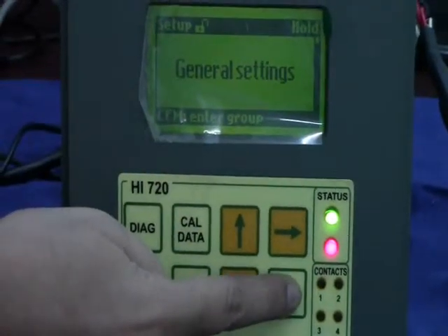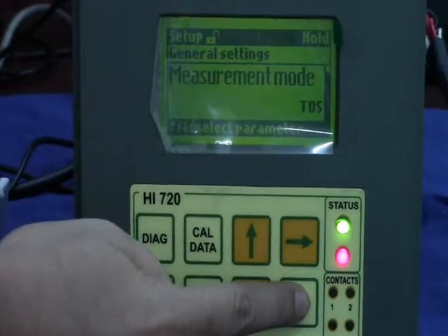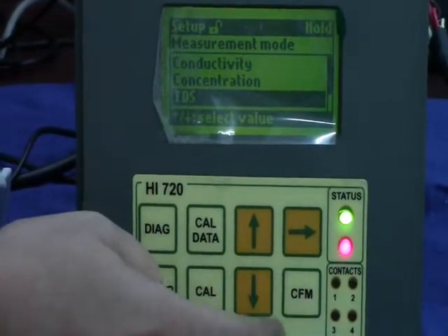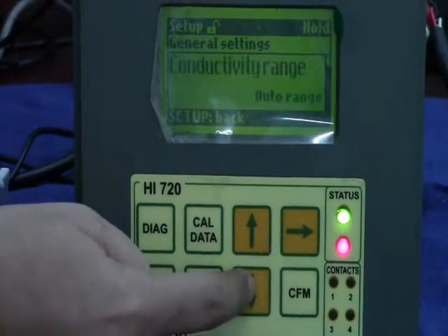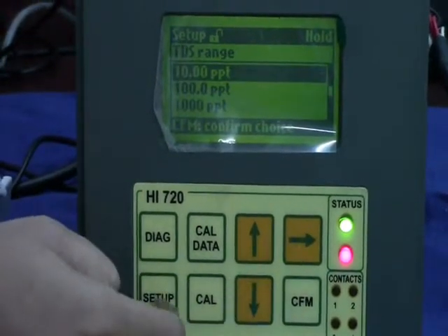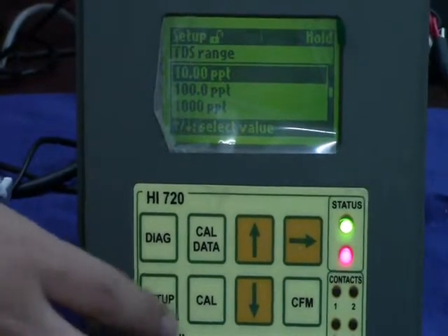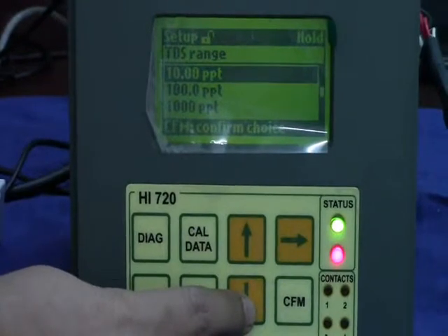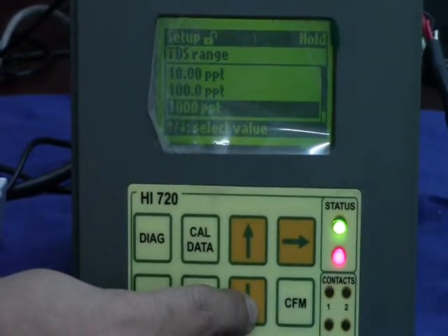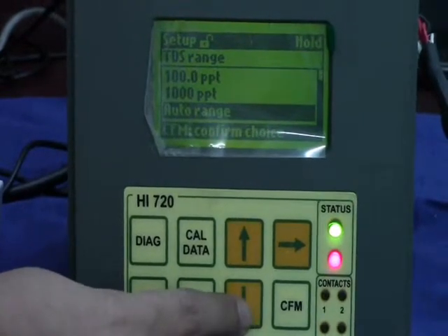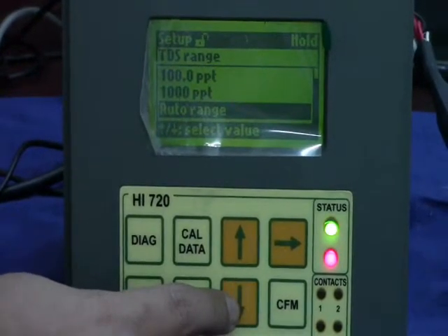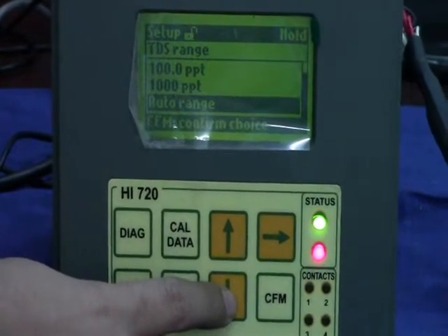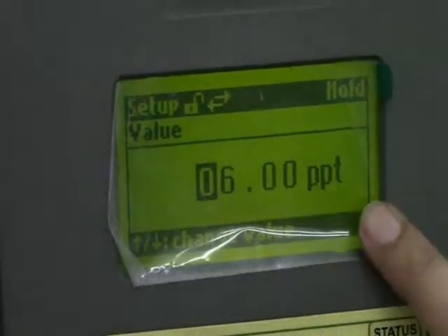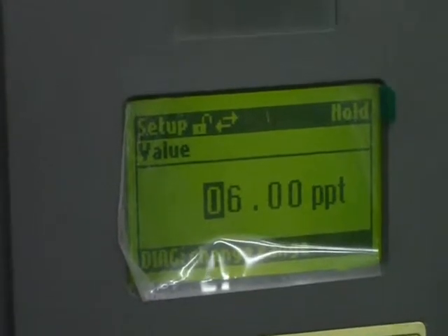Getting into the general settings, measurement mode has been selected as TDS. TDS range has been selected as 10 ppt. Customer can select a range from 10 ppt to 100 ppt. He can also select an option of auto range, wherein the controller will sense the sample and select the range. As you can see, the set point has been set to 6 ppt. 6 ppt is 6000 ppm, confirming the value and coming out of the setup.